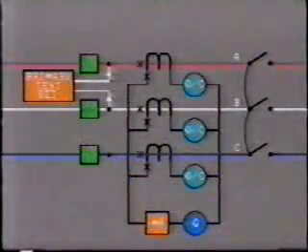The next test is to ensure that the CTs are connected the right way around, that is, they are in balance. For this test, a temporary short circuit is placed across the primary conductors. In this particular example, test current is passed through the A phase CT primary conductor and then back through the B phase CT in the opposite direction.